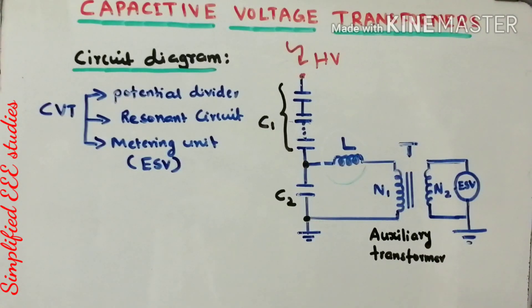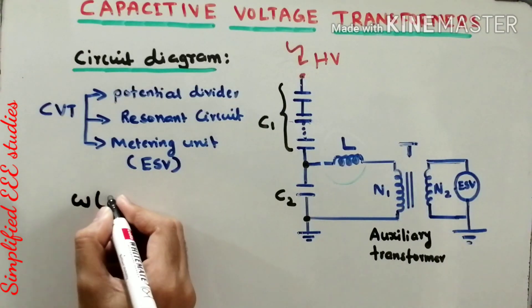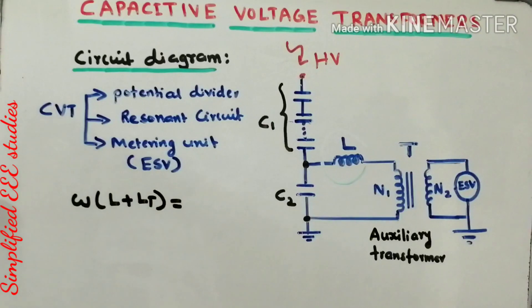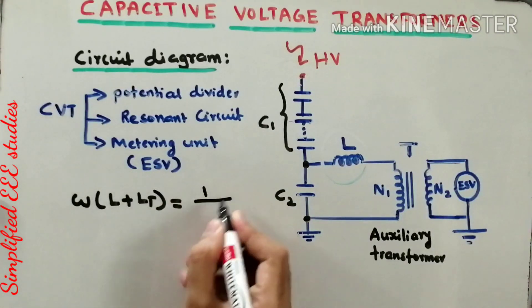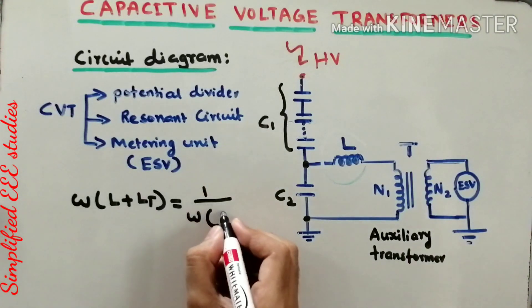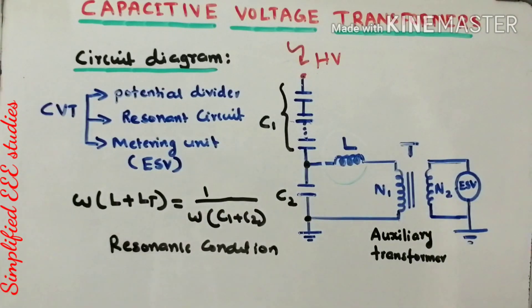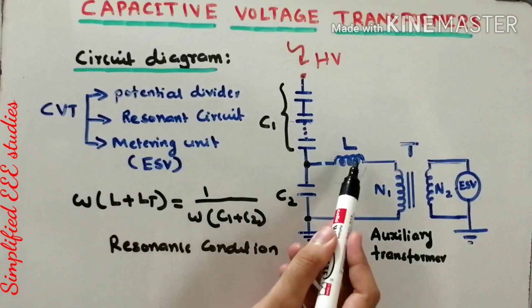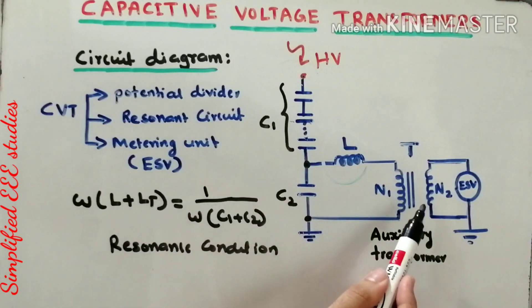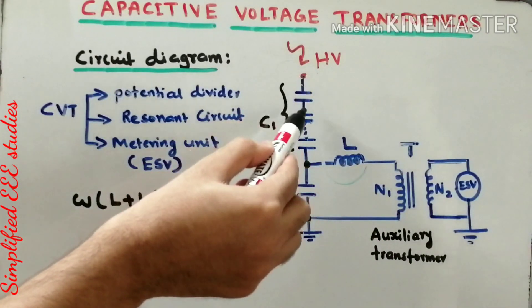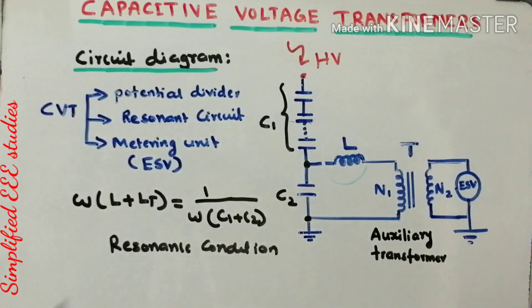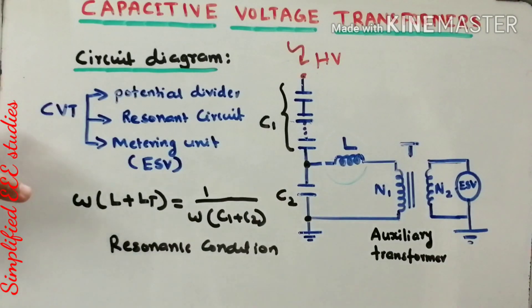In order to maintain the resonance condition, you need to follow this equation: ω(L + Lt) = 1 / [ω(C1 + C2)]. Here ω is the angular frequency expressed in radians per second, L is the value of the inductor in Henry, Lt is the inductance of the auxiliary transformer, and C1 and C2 are the values of the high voltage and low voltage capacitances respectively. While designing the CVT, you must ensure that the circuit follows the resonance condition.